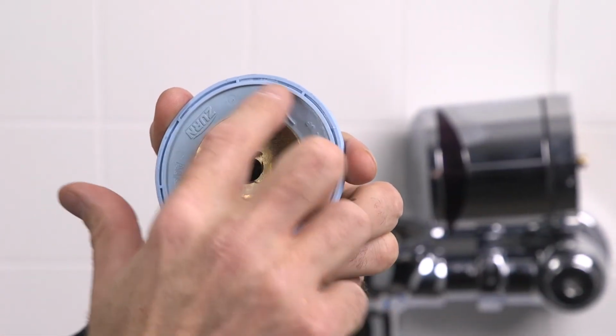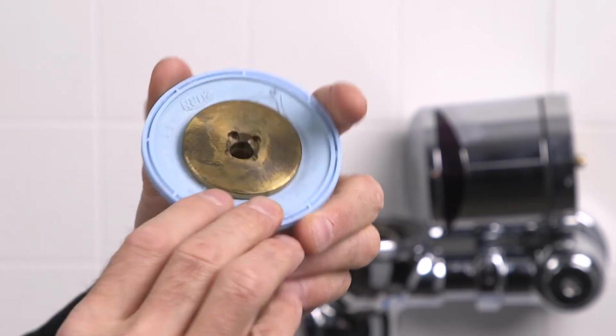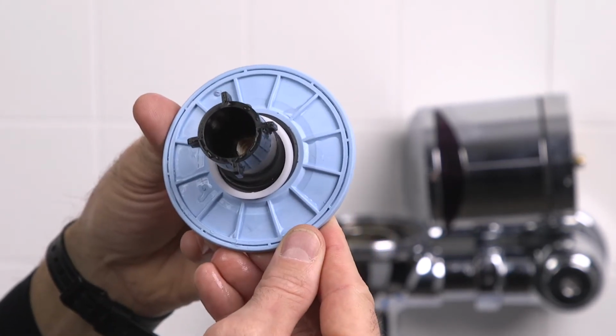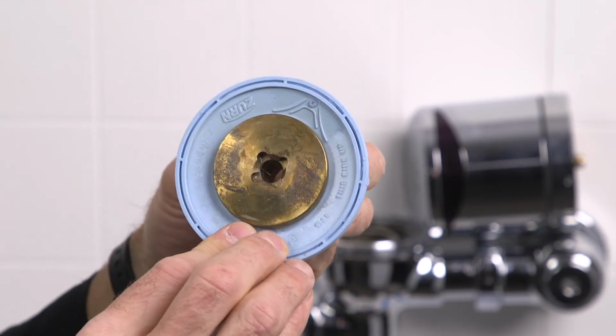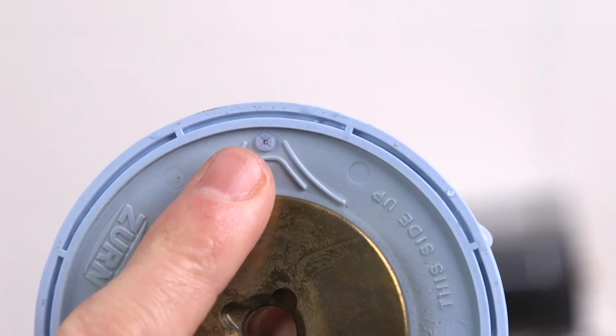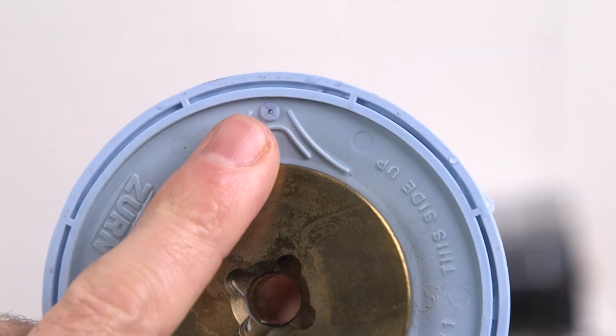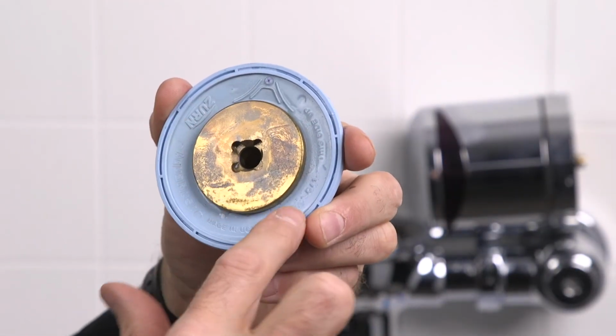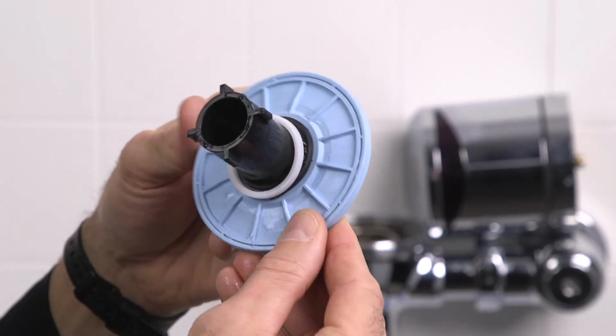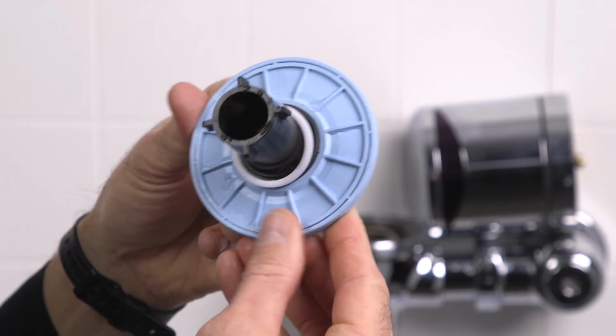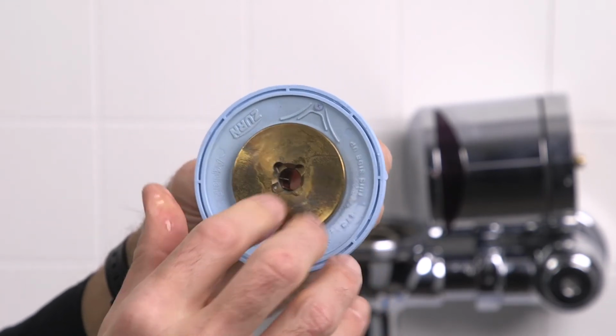Inspect the diaphragm for damage or punctures. If it's damaged, you'll need to replace the diaphragm. Inspect the bypass orifice. If it's enlarged, damaged, or missing, you'll need to replace the diaphragm. Ensure that you have the correct type of diaphragm for your fixture. If it's not the correct one, you'll need to replace it with the proper diaphragm.